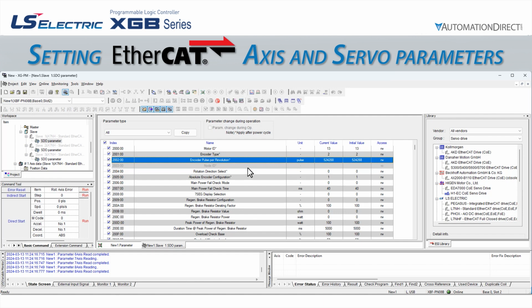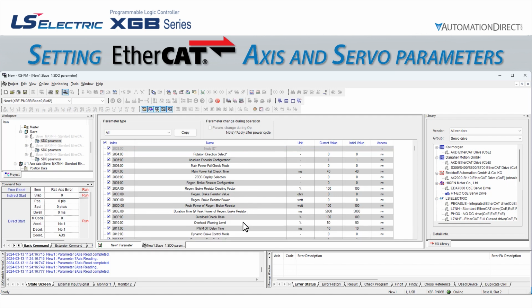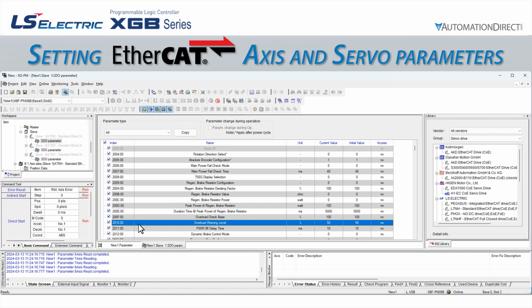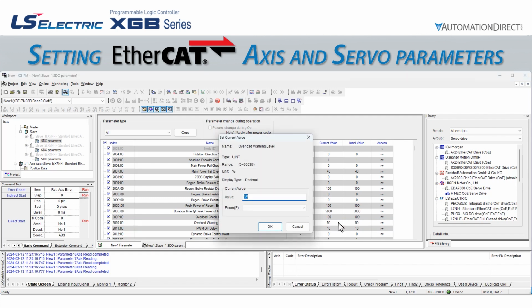If we scroll down slightly, we find this parameter is at index 2010:00. Its default and current values are both set to 50%, and it is able to be read and written. Let's change this value to 75% instead. To do this, we simply double-click anywhere in the row. This will open the Set Current Value pop-up window for this parameter. We can change the 50 to a 75 and click OK.